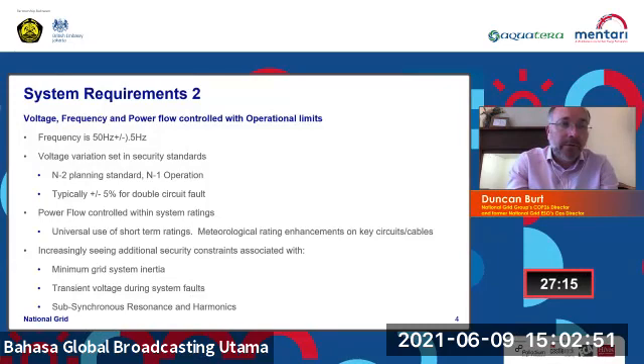Typically, in terms of voltage variation, we plan to plus or minus 5% voltage variation for a double circuit, though it can go greater than that. And obviously, the power flow on the system is continually managed within system ratings. There is universal use right across the system of short-term ratings for 10 minutes, 20 minutes, up to 6 hours, where you can overload the system for short periods to handle a fault. And we have meteorological enhancements to allow for hotter or colder weather, which would allow for more cooling on all of the key circuits and cables on the system. And the system has run like that for the last 50, 60 years.